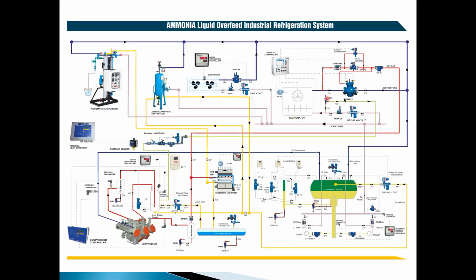You have a defrost relief valve over here, which can be set to around 10 degrees centigrade, or around 5.5 to 5 bar pressure, which will drain all the liquid back into the system. It can be taken into the LP vessel, or it can be taken into an intermediate vessel if we have multiple high stage, booster or low temperature intermediate vessels. This is how the hot gas defrosting circuit works.